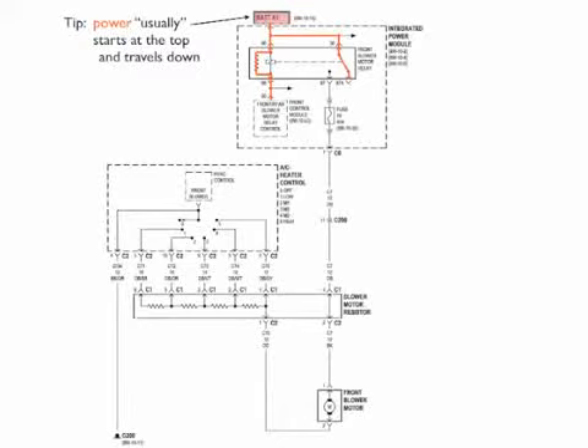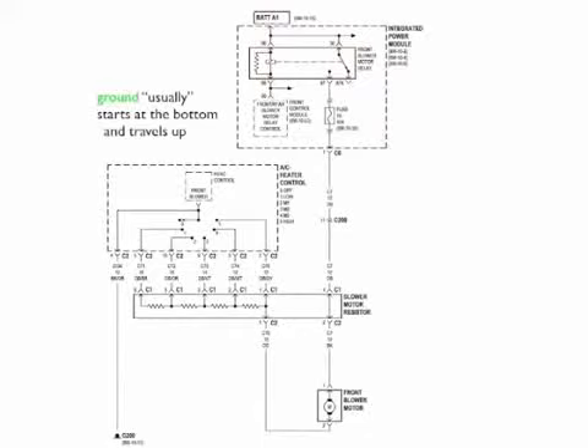It travels downward until it gets an open. At the front blower motor relay, you'll see that switch is open, so it stops, and then it goes down through the electromagnet, and it stops because there's no ground there. Now remember, it always stops at an open. And ground usually starts at the bottom of the page and travels upward. This is how they're usually drawn, and again, it will stop at an open.